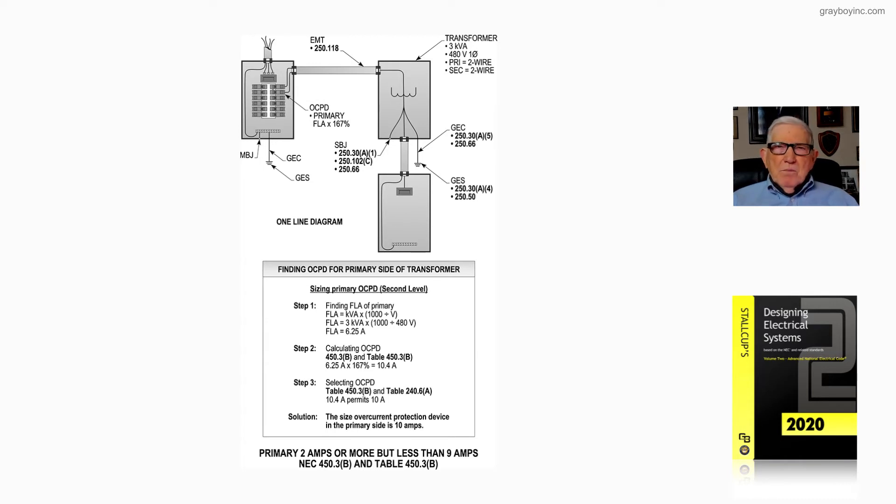the primary overcurrent device can protect the primary side of the transformer, the windings, the secondary side of the transformer, and everything is considered protective if you size it properly in relation to the ratio of the primary to the secondary voltage.